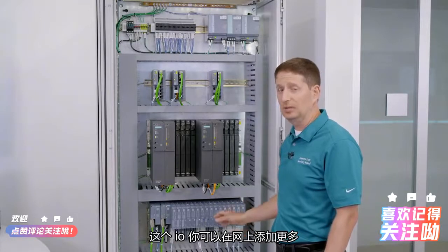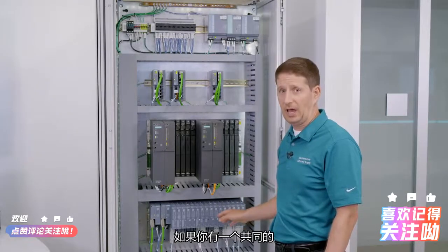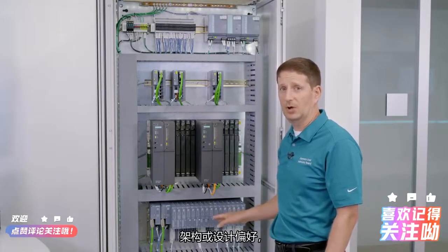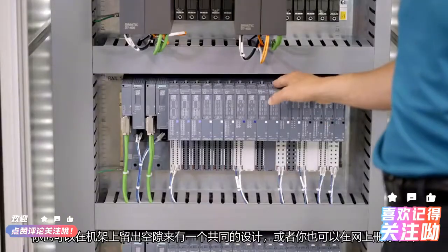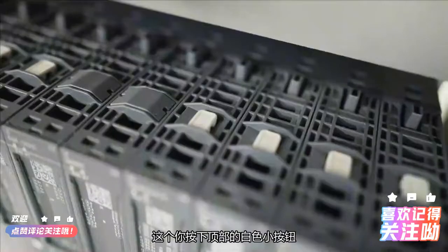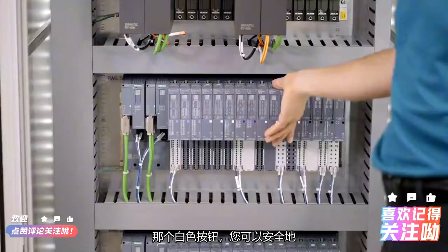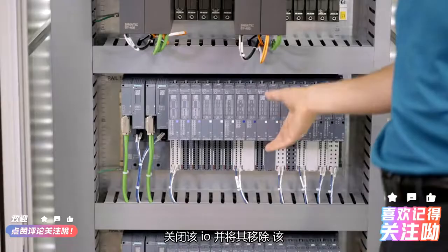This I/O, you can add more online. You can also leave gaps in the rack to have a common design if you had a common architecture or preferences for design. Or you could also remove cards online. This little white button on top, you press that white button and you safely de-energize that I/O and remove it.